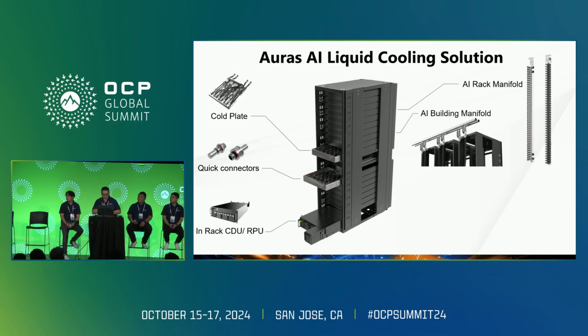Beside the basic manifolds, we have successfully developed a new innovative rack building manifold that features monitoring and protection functions. Not only can the operating temperature for rack and pressure be monitored at any time, but with the security function, if there is any liquid leaking in the system, it can cut off immediately, at the same time when the system is shutting down as well.